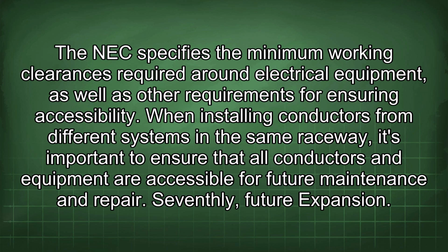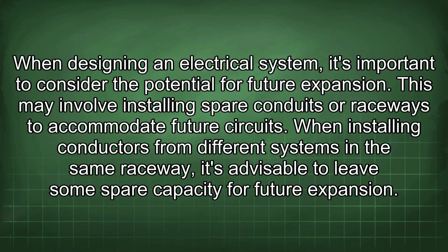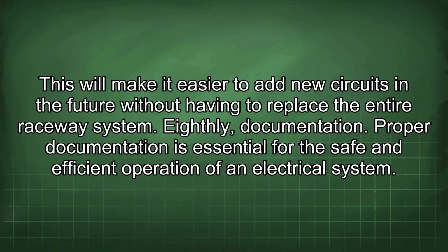Seventhly, future expansion. When designing an electrical system, it's important to consider the potential for future expansion. This may involve installing spare conduits or raceways to accommodate future circuits. When installing conductors from different systems in the same raceway, it's advisable to leave some spare capacity for future expansion. This will make it easier to add new circuits in the future without having to replace the entire raceway system.